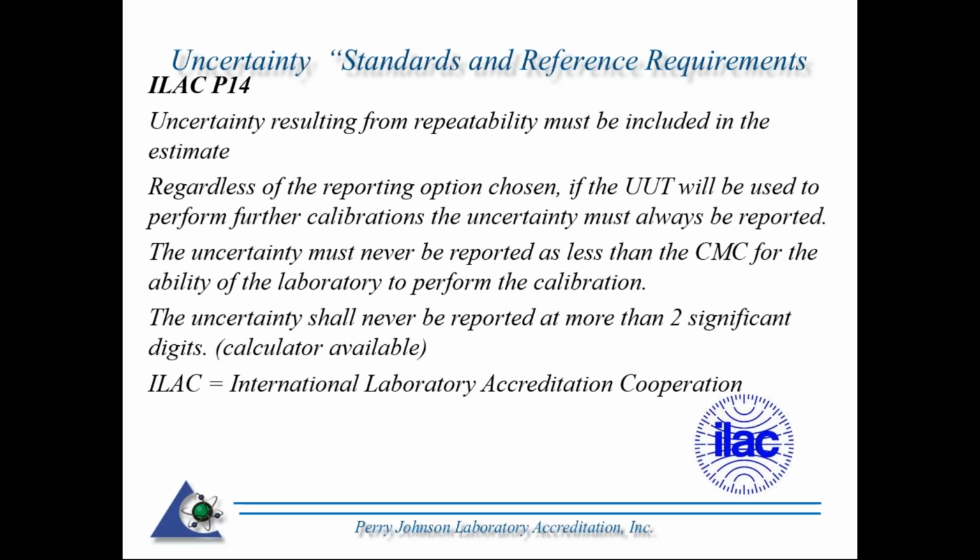The uncertainty must never be reported at less than the CMC. CMC is calibration and measurement capabilities. Used to be BMC, best measurement capabilities, for the ability of the laboratory to perform the calibration. So a CMC is, for example, when you look on an accrediting body's website, look at calibration, you'll typically, and we'll see some examples here, have a range with CMCs. Those CMCs are the calibration and measurement capabilities of the organization.